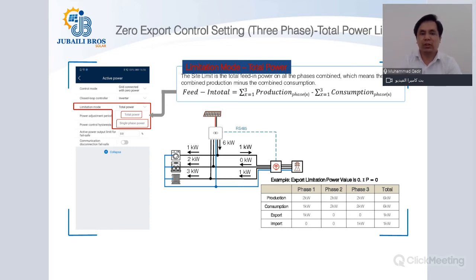Zero export control setting with the three-phase total power limit. Now, in case of three-phase, you have two options. You can control the output of solar inverters with the option of total power limitation or the single phase limitation. First, we will speak about total power limit.